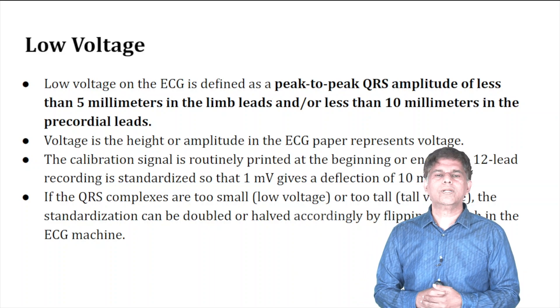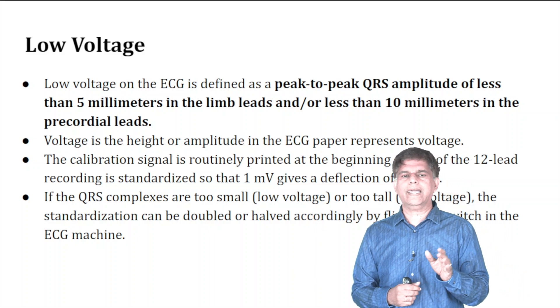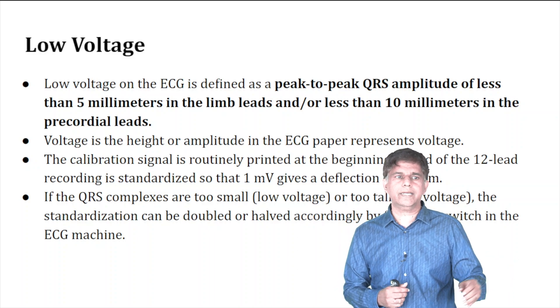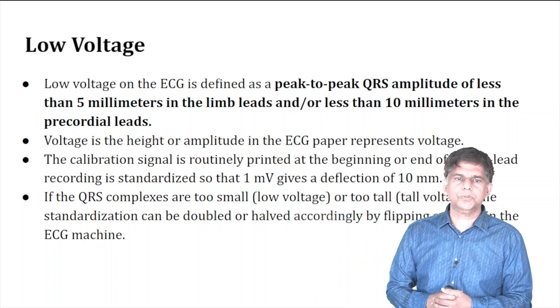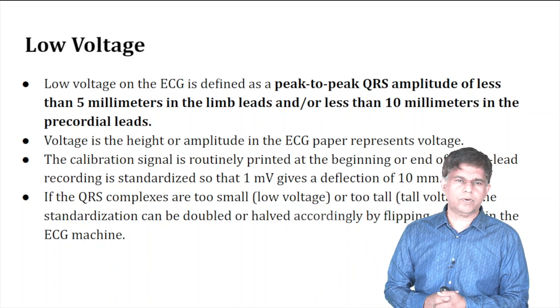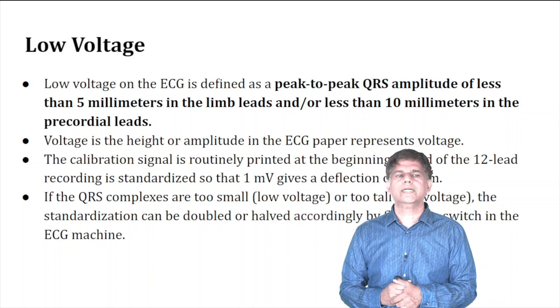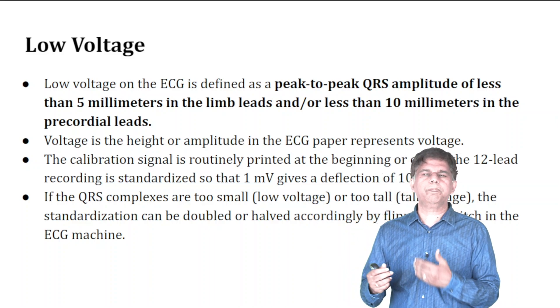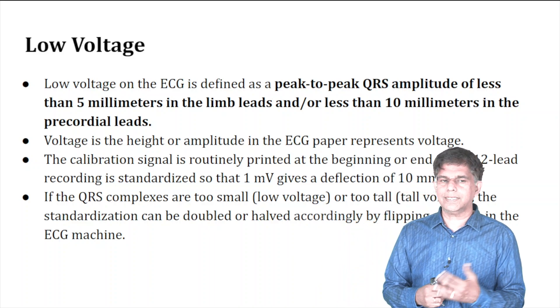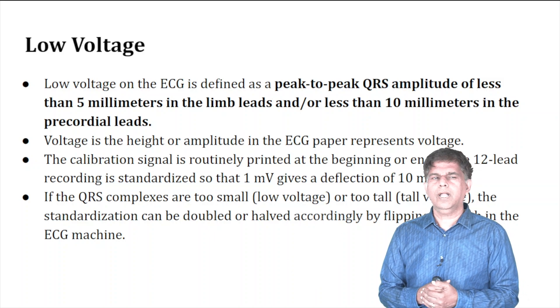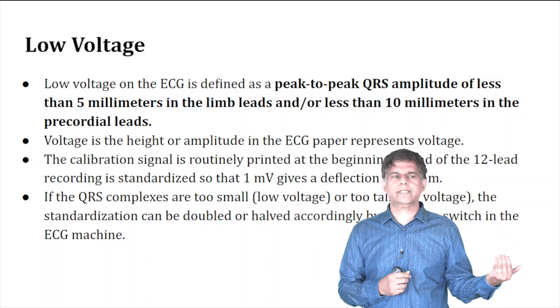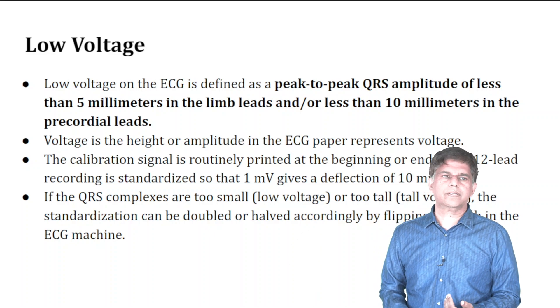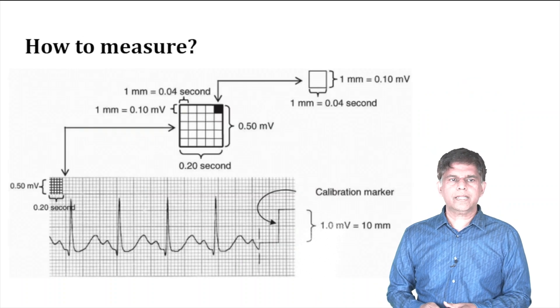The calibration signal is routinely printed at the beginning or end of the 12-lead EKG — you can usually see it on the left side. If the QRS complexes are too small (low voltage) or too tall (high voltage), the standardization can be doubled or halved by flipping a switch on the EKG machine. Always check the calibration on the left side and compare it.